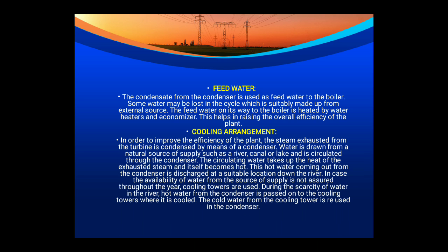To improve efficiency, the steam exhausted from the turbine is condensed in the condenser. Water is drawn from a natural source such as a river, canal, or lake and circulated through the condenser; this circulating water absorbs heat from the exhaust steam and becomes hot. When availability of water from the supply source is not assured throughout the year, cooling towers are used. During water scarcity, hot water from the condenser is passed to the cooling tower where it is cooled. There are two types: forced draft cooling tower and natural draft cooling tower. The cooled water from the cooling tower is then reused in the condenser.